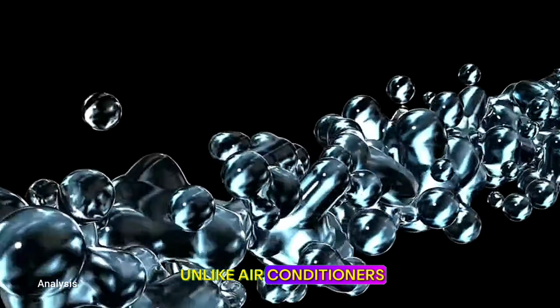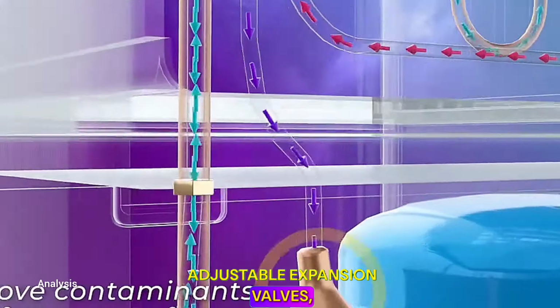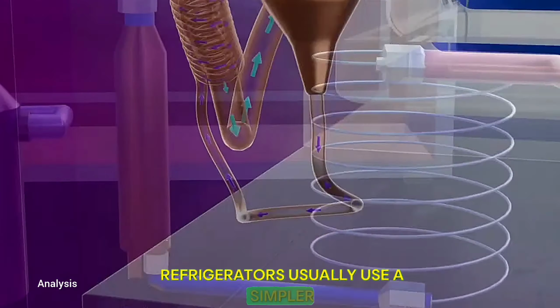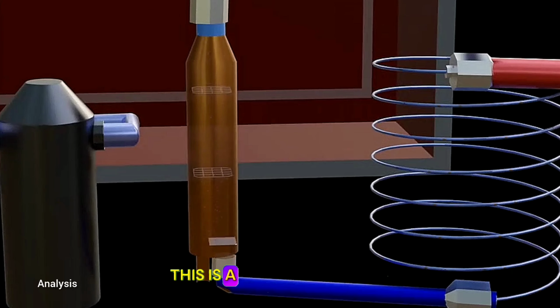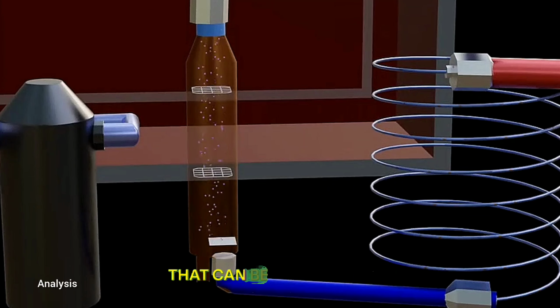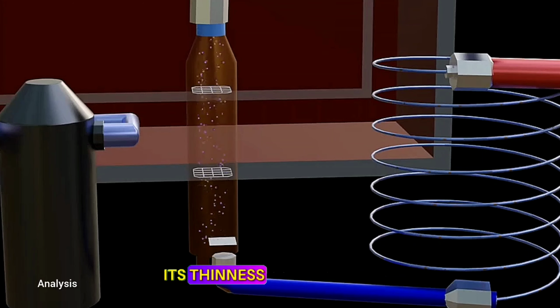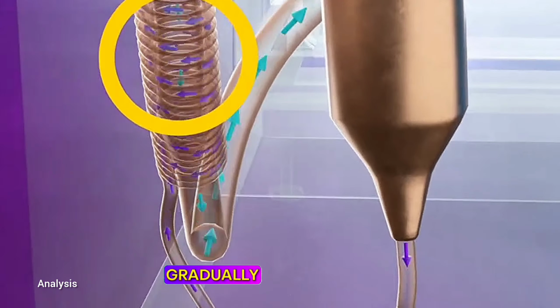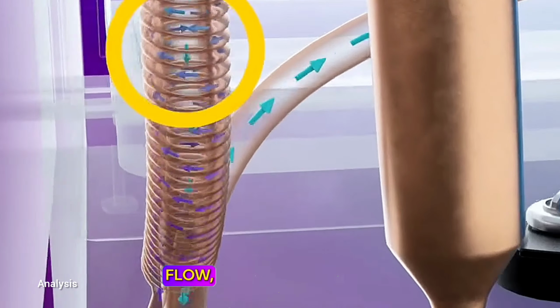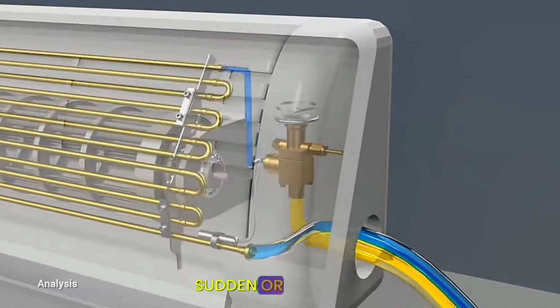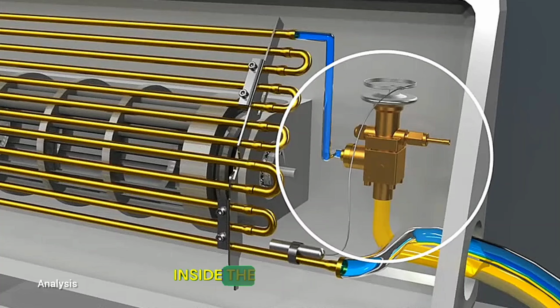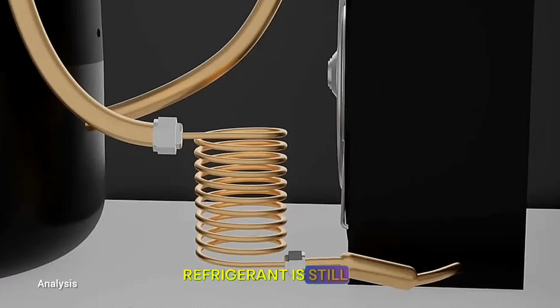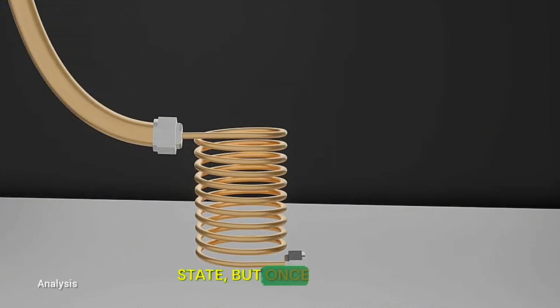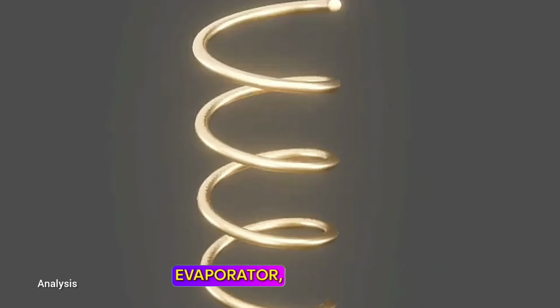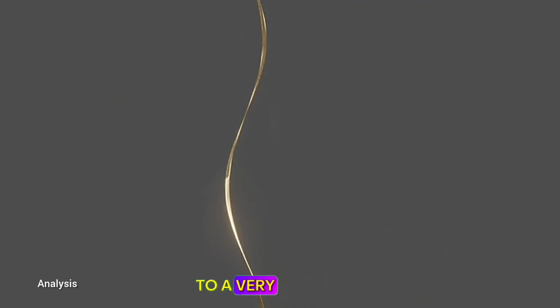Unlike air conditioners, which use adjustable expansion valves, refrigerators usually use a simpler capillary tube. This is a thin, long copper tube that can be several dozen centimeters or even a meter or 2 in length. Its thinness and length are designed to gradually lower pressure and control flow, so the pressure drop isn't too sudden or unstable. Inside the capillary tube, the refrigerant is still in a high-pressure state, but once it sprays into the evaporator, its pressure suddenly drops to a very low level.